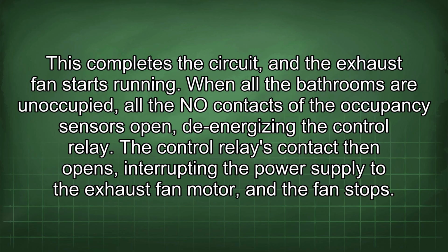When all the bathrooms are unoccupied, all the NO contacts of the occupancy sensors open, de-energizing the control relay. The control relay's contact then opens, interrupting the power supply to the exhaust fan motor, and the fan stops.